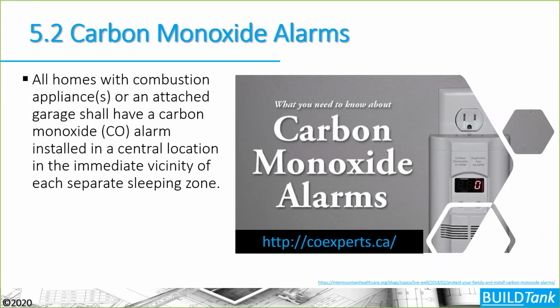Regardless of if you're using sealed combustion or power vented appliances, any type of house that has a fuel burning appliance in it also must have a carbon monoxide detector in it. And it's important to understand the different types of carbon monoxide detectors. Most carbon monoxide detectors don't sound at very low levels here. And low levels of carbon monoxide can be quite unhealthy for the occupants. So if you go to this website, coexperts.ca, you can get more information on that. But the carbon monoxide alarms that they make, that CO Experts, are amazing at how well they work and how they can pick up low levels of carbon monoxide in a house here.